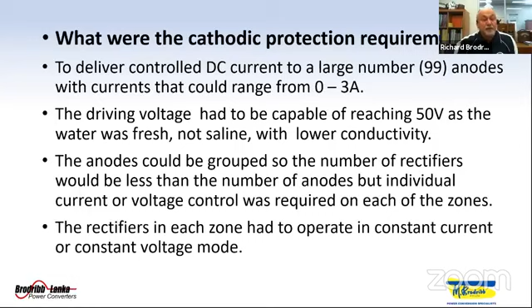To save money and make it easier to control, the anodes were grouped so the number of rectifiers would be less than the number of anodes. So some anodes were paralleled, but individual current or voltage control was required for each of the zones. Even though the anodes were paralleled, you had to have discrete control over the zones, like a concrete system, but this was like a concrete system writ large. The rectifiers in each zone had to operate in either constant current or constant voltage mode.